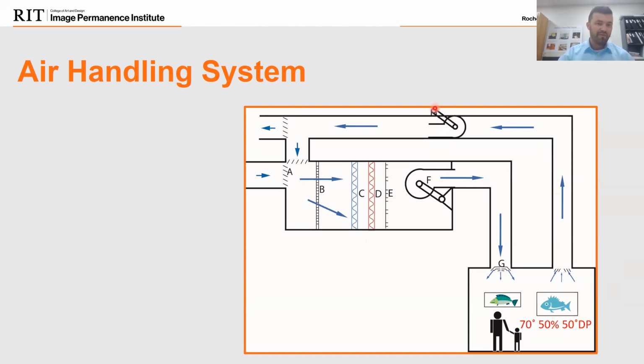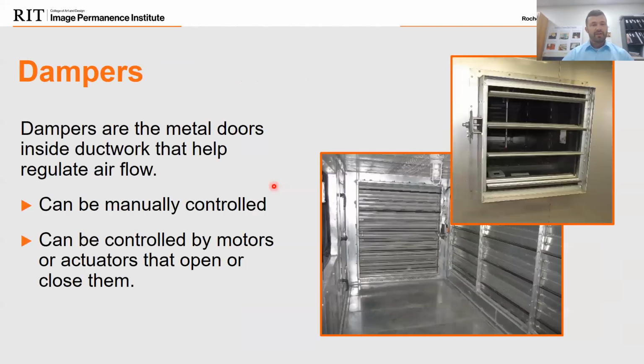We have a return fan here that's doing this work. It's pulling the air through the duct. And we're going to go here. Our first stop is going to be these dampers and this outside air. So first of all, what are our dampers? For those of you who aren't aware, dampers are just the metal doors inside ductwork.